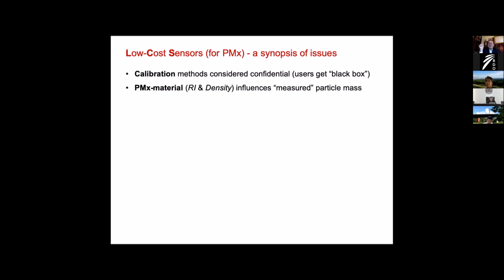However, the refractive index is less, well, I would not say less important, but it influences the nephelometric measurement, where we measure light scattered from many particles at the same time, not as strongly as single particle measurement. And the signals are more stable the more polydispersed the particle material is.